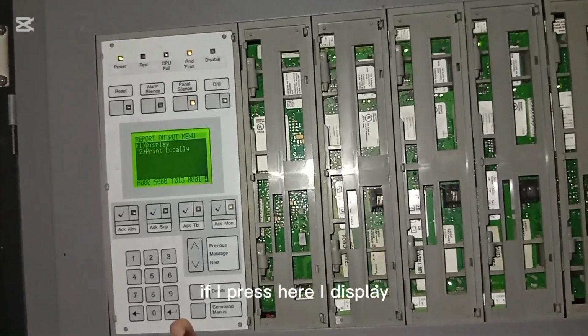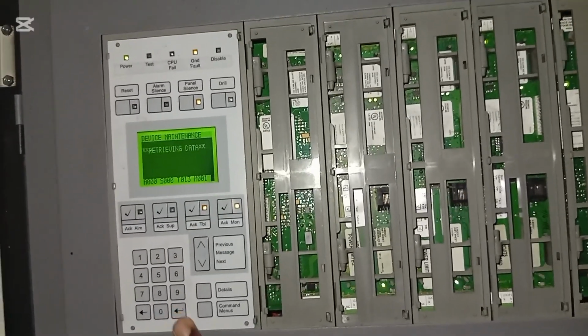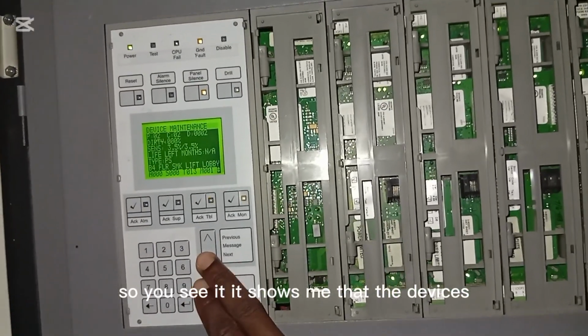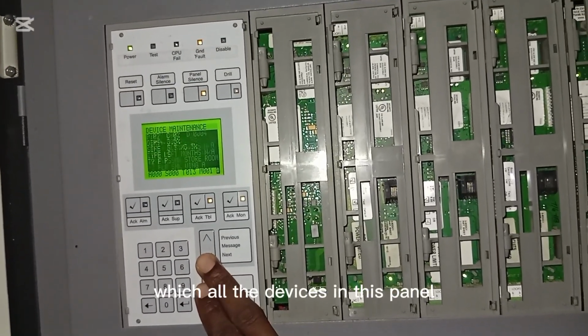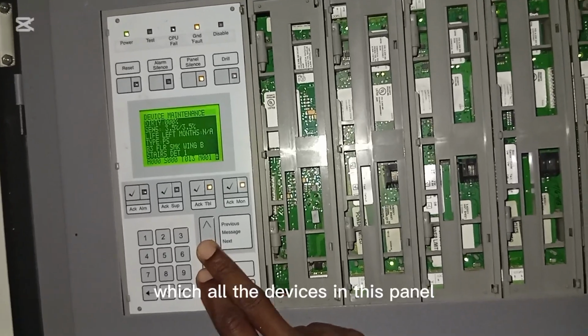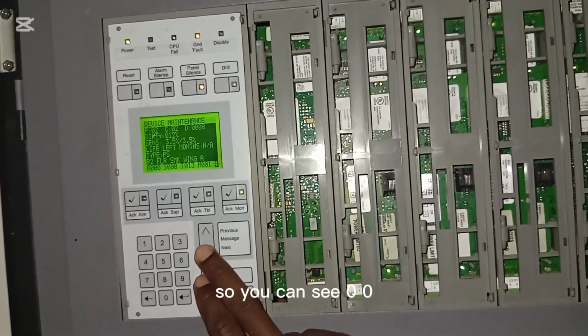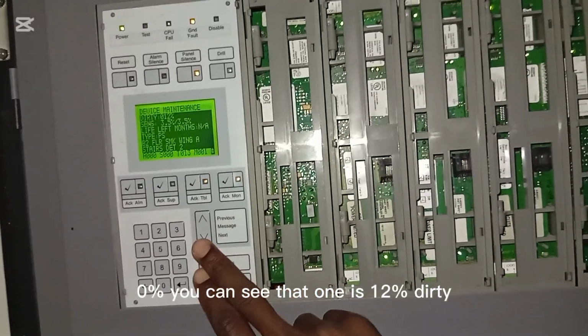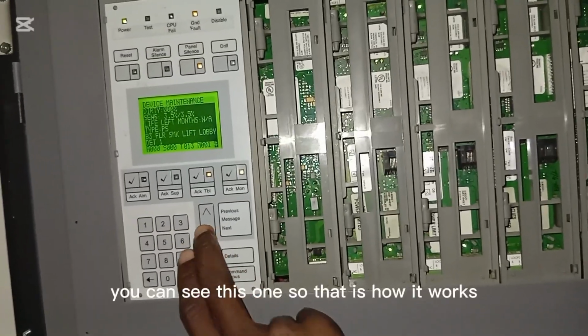If I press here, I display. So you see, it shows me all the devices in this panel. You can see 0%. You can see that one is 12% dirty. You can see this one. So that is how it works.